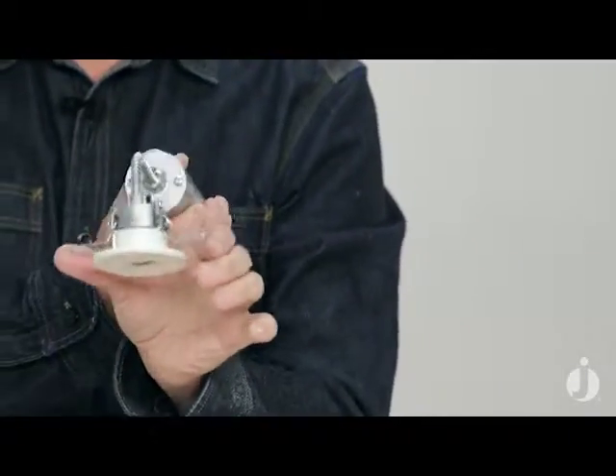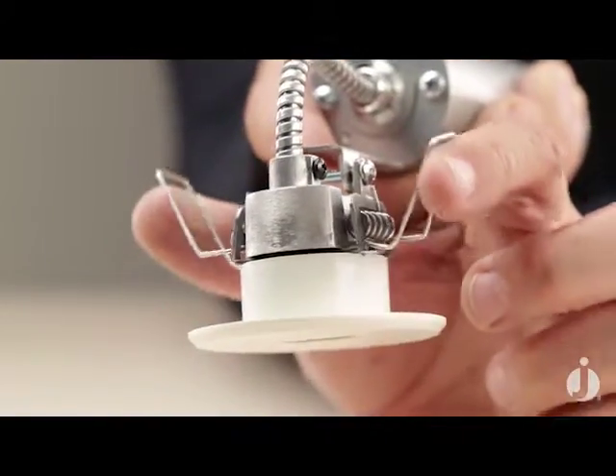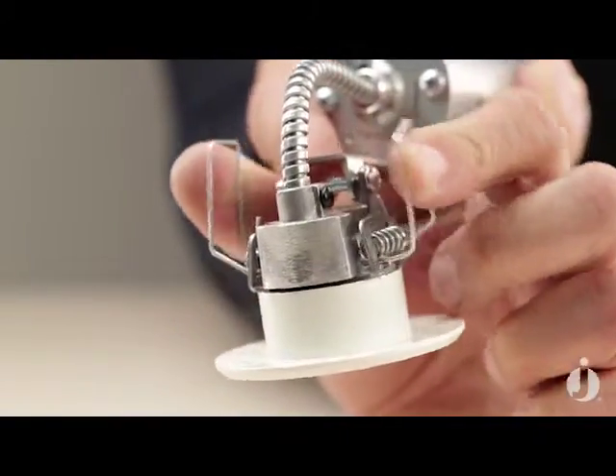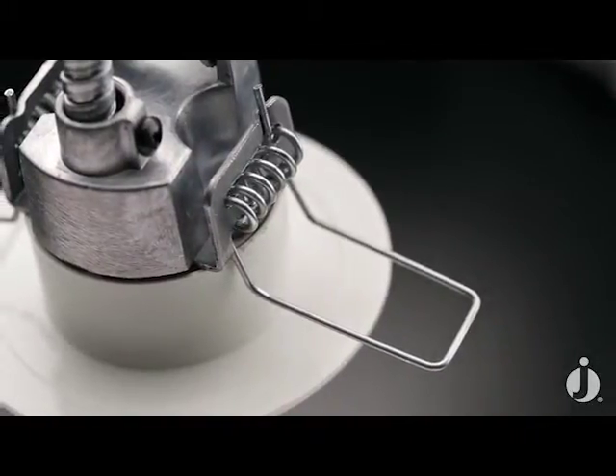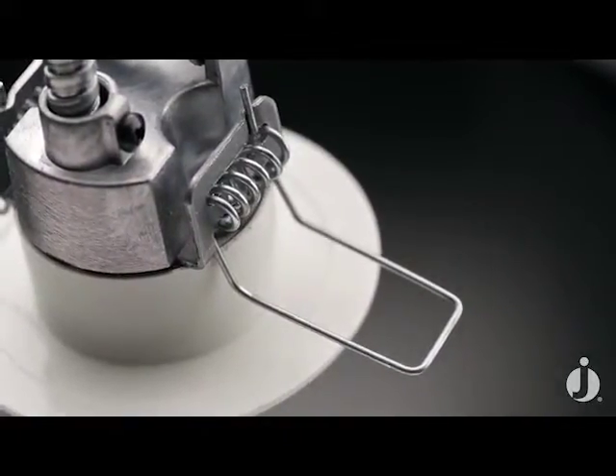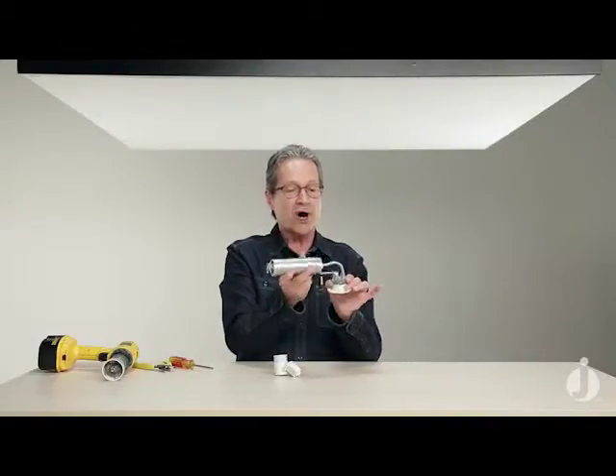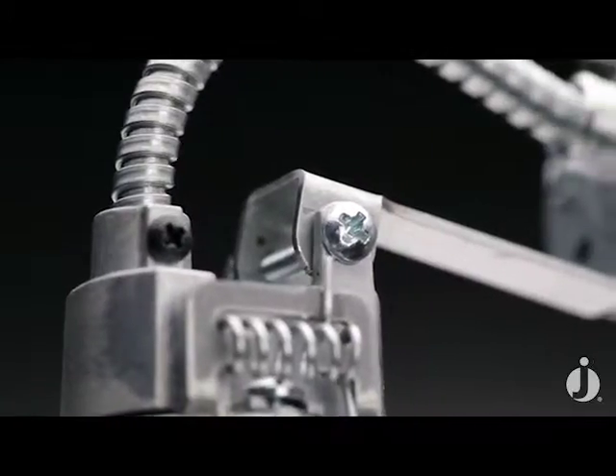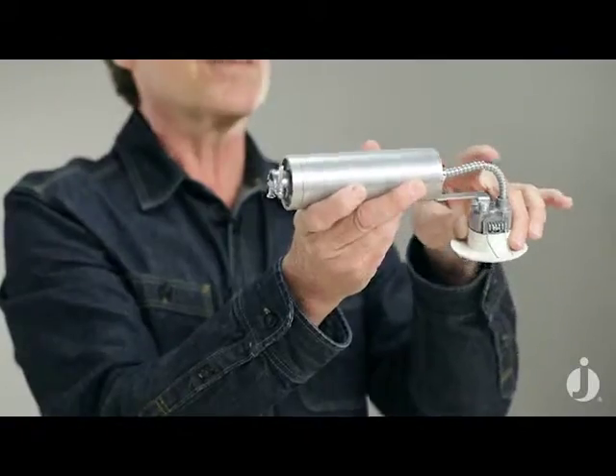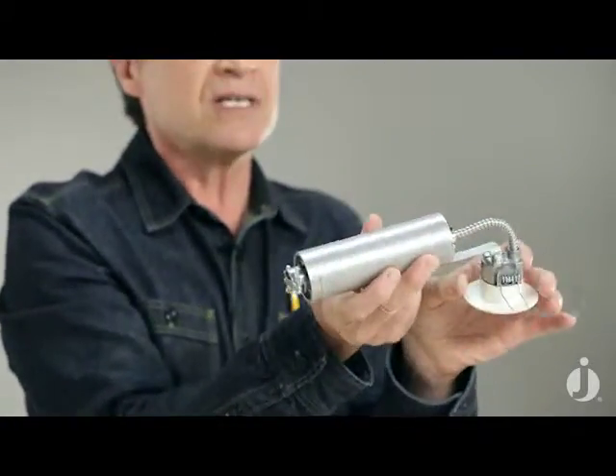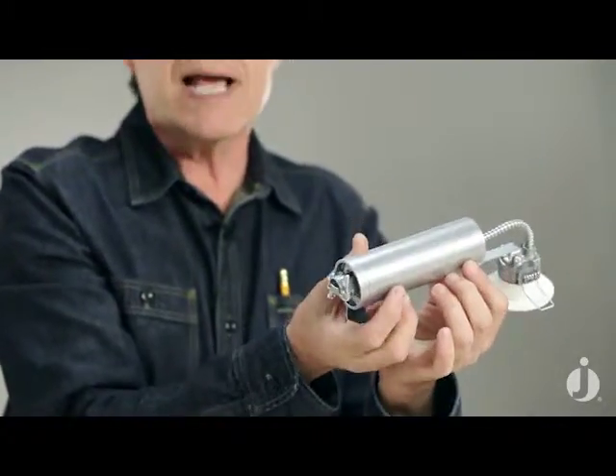The product actually is held in place by some springs that are flexed up as I feed it through the hole and then released. These springs will accommodate a ceiling or surface up to 3/4 inches in depth of any material, including wood. You can see that that monopoint part is actually attached with a kind of a flexible hinge. Here's my power, and here's my support to a wiring chamber, and in this case, an electronic transformer. The electronic transformer must be compatible with an electronic low-voltage dimmer.